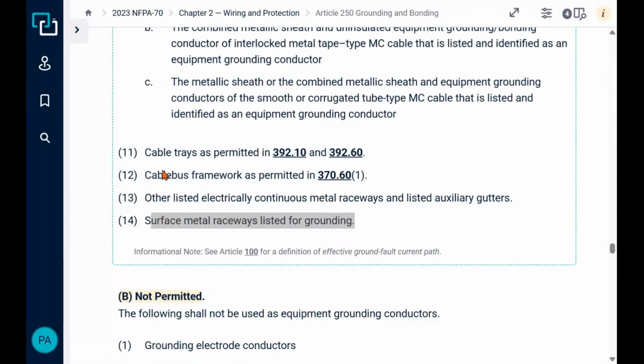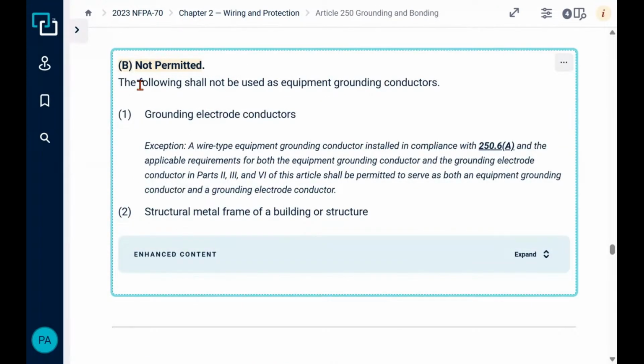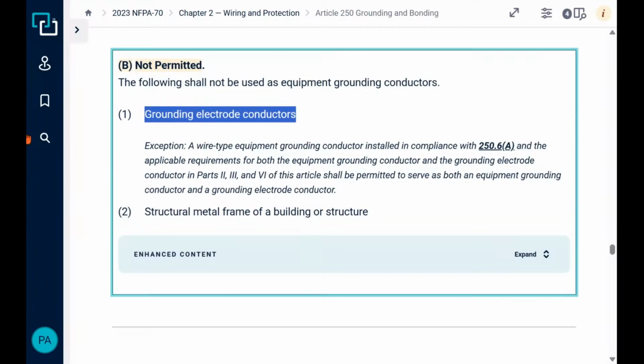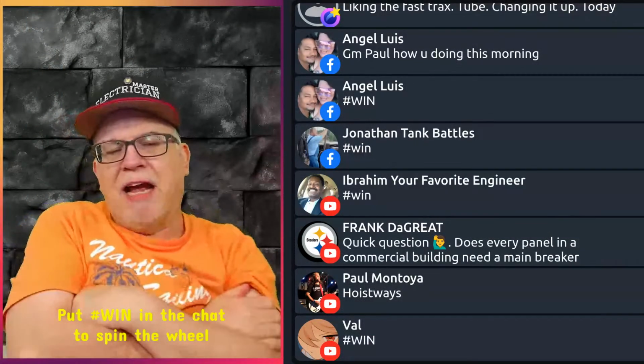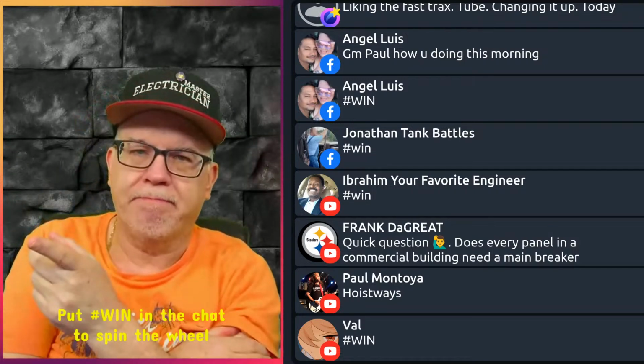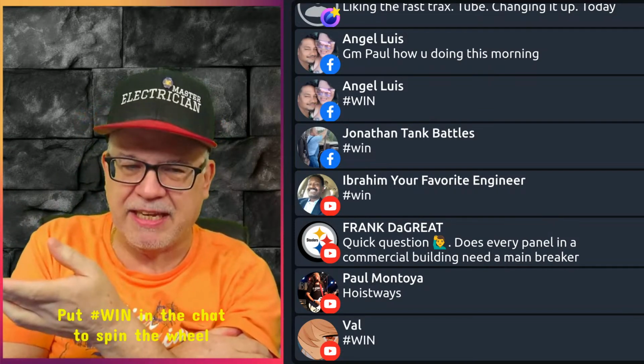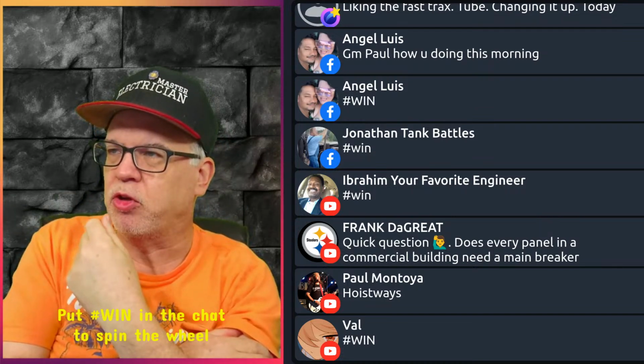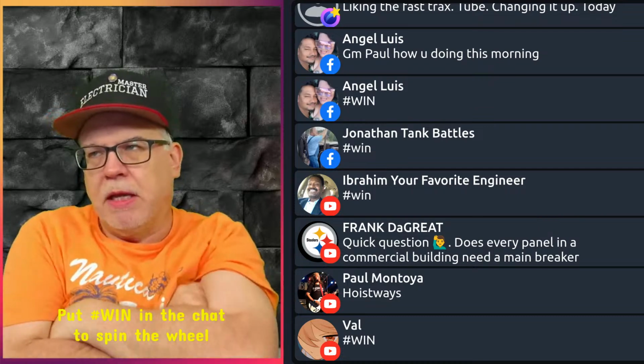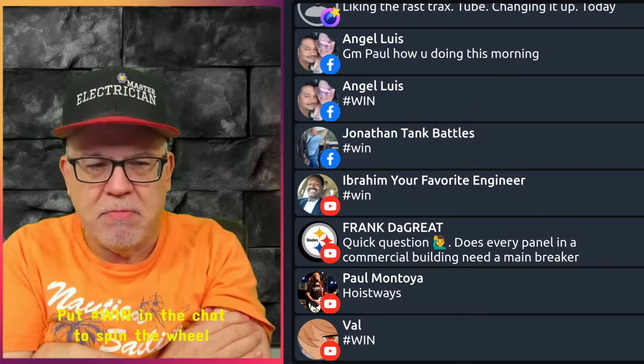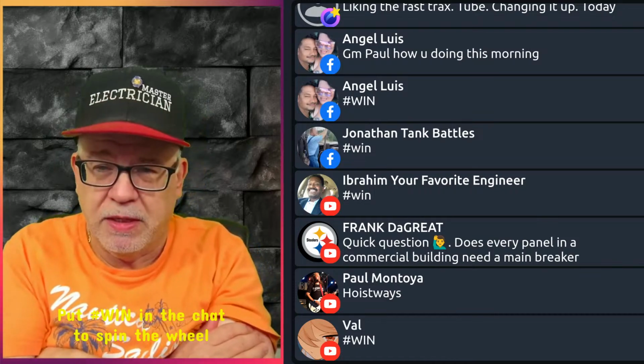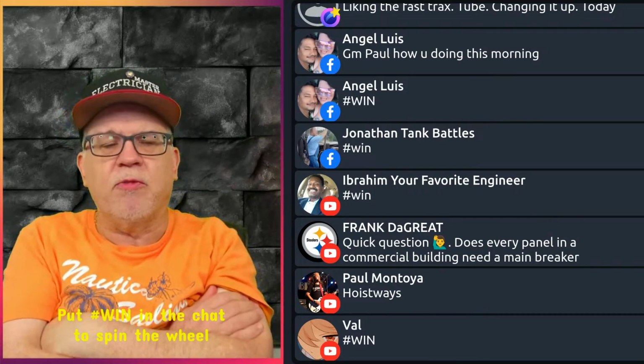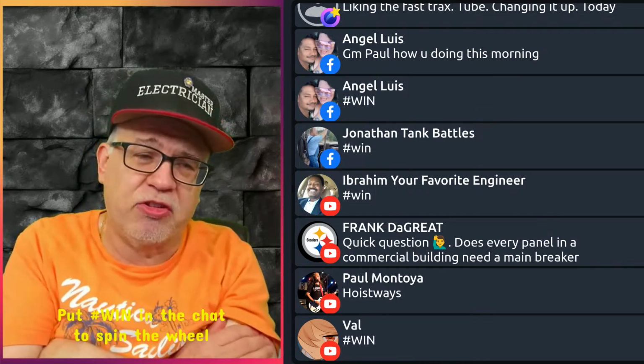So what does that mean? Let's go to the code real quickly and show you this in the code. So this is use is not permitted right here. Okay. So the following shall not be used as an equipment grounding conductor. The general rule is going to be grounding electrode conductors. Okay. Now here's some things I want to tell you about with that before we look at the exception. A grounding electrode conductor must be run what? Unbroken. Now there are allowances for splicing it, irreversible crimp, or if you use the Cadweld. Okay. Other than that, taking a GEC and running it from an electrode up to the panel, it's required by the requirements in 250.24 that the GEC has to be connected to the grounded conductor.